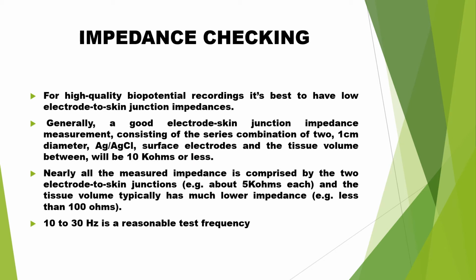And next we have impedance checking. Impedance checking between a pair of electrodes attached to the skin surface is a very simple method to verify the conductive quality of electrode-skin junctions. For high quality biopotential recordings, it's best to have low electrode-to-skin junction impedances.